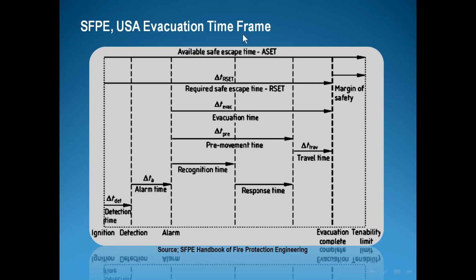So our main parameters here to define if this building needs a smoke management system or not are the ASET and RSET. And ASET shall be established based on your tenability criteria. From these two times, normally the available one shall be greater than the required, because the required safe escape time could be increased by a lot of equipment, but it would reflect a very bad cost impact for the project.